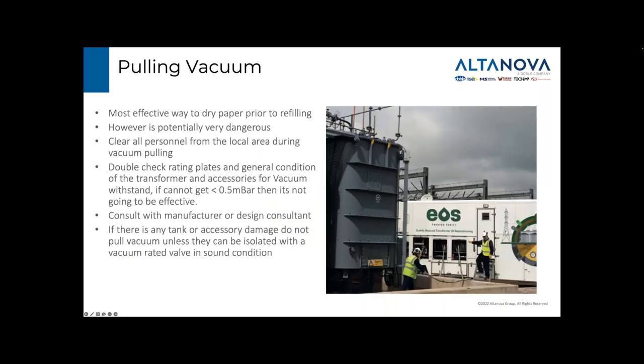Pulling vacuum might be the most effective way to dry the paper prior to filling. However, it is inherently dangerous. All personnel should be located outside the area, and it should also be barriered off to prevent unauthorized access. Double check rating plates and paperwork to ensure full vacuum can be sustained. And if you can't pull full vacuum, it's not going to be effective, so don't do it. If in any doubt, contact the manufacturer or design consultant, and if there's still some doubt, or there are obvious signs of damage to the transformer or accessories, do not perform this task, as there is no way of knowing how much vacuum the damaged compartment can sustain before it fails.